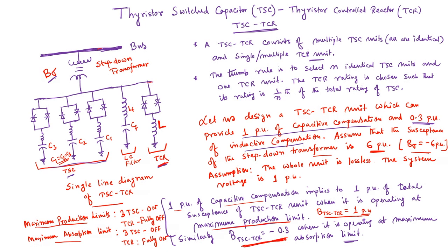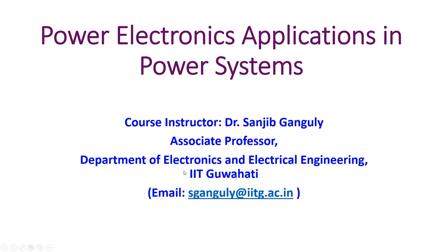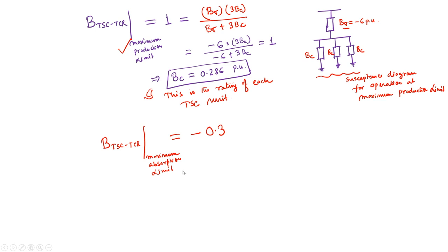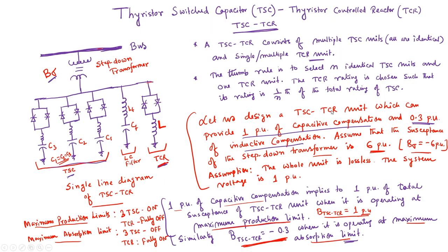So BTSC-TCR is minus 0.3 when it is operating at maximum absorption limit — this is according to the problem statement. So what we can write is this: now when this is operated at maximum absorption limit, all the TSC will be turned off, as I mentioned before, and the TCR will be fully turned on.